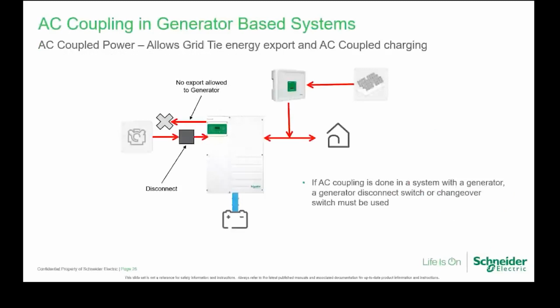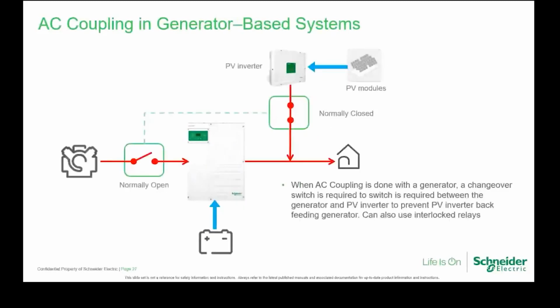So while we're here, we have an AC coupled system. When you have an AC coupled system with a generator, you need a generator disconnect switch or change-over switch. As you can see over here, there's a change-over switch. One is normally open, that one's normally closed. And when you change over from one to the other, for example, when the generator starts, you can have it automatically detect for the contactor so that it closes, and this other one, the PV inverter, actually opens. We can use interlock relays if you like.